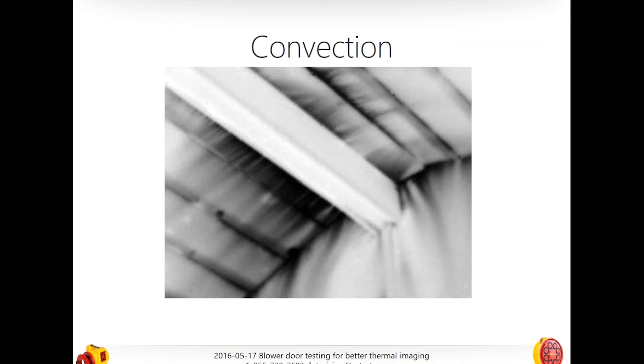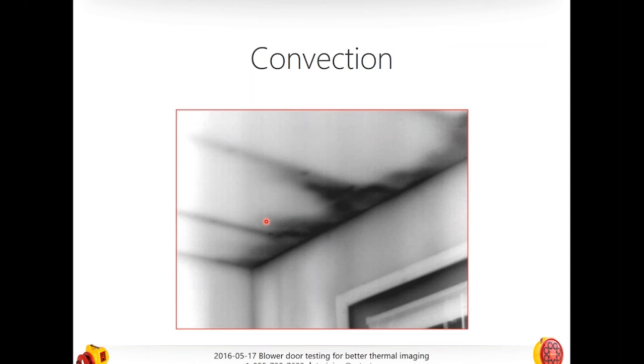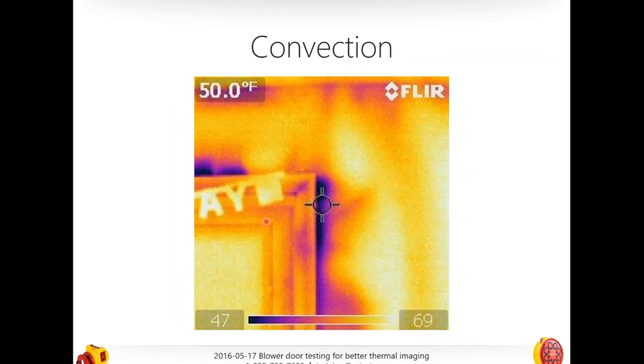Higher pressures may speed things up a little, but it all depends. It is possible that if you depressurize a house — which you need to do to see leakage from the inside — and it's very cold out with a big temperature difference, you could actually make everything so cold that you can't see anything. Andrew's concern is that you may normalize the house pressure with the outside too quickly at high speeds.